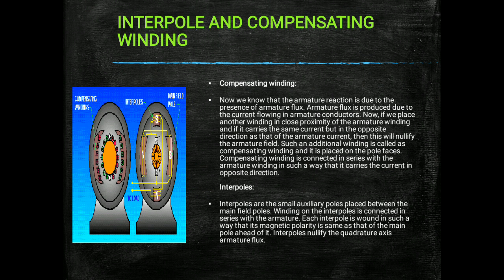The compensating winding is connected in series with the armature winding so that it carries current in the opposite direction. Now, what are interpoles? You can see the image of interpoles and compensating winding here. Interpoles are small auxiliary poles placed between the main field poles. The winding on the interpoles is connected in series with the armature. Each interpole is wound so that its magnetic polarity is the same as that of the main pole ahead of it. Interpoles nullify the quadrature-axis armature flux, thereby minimizing armature reaction, as does the compensating winding.